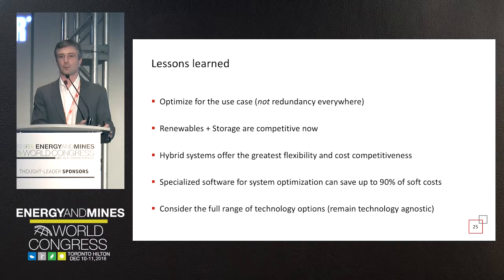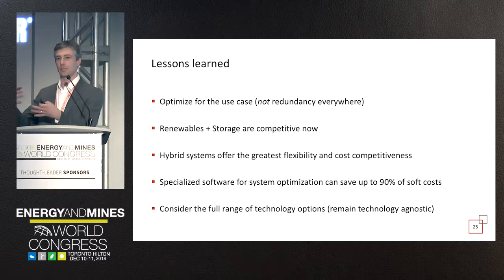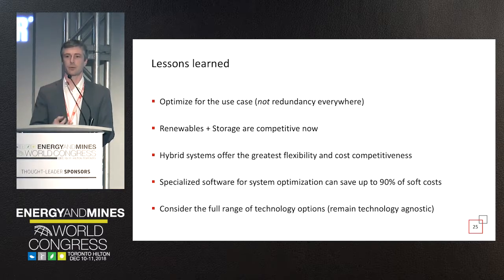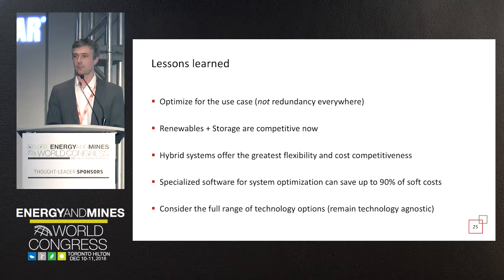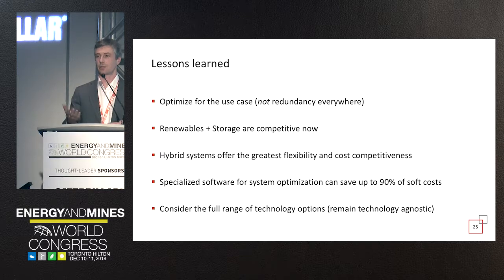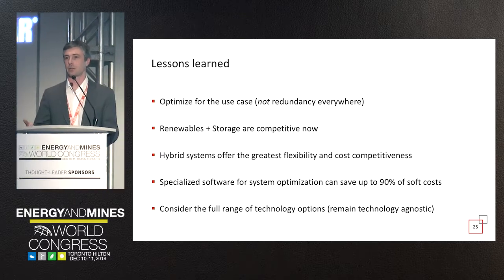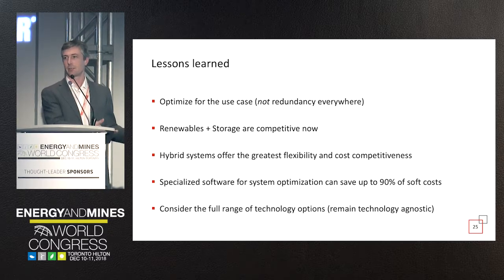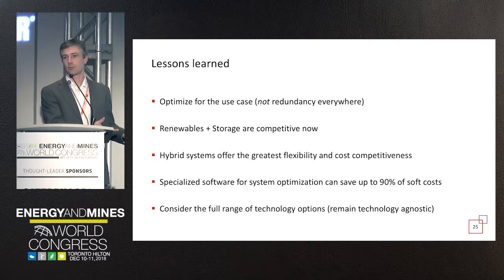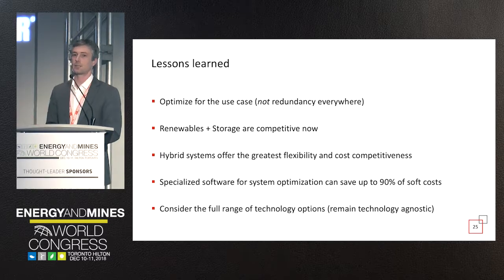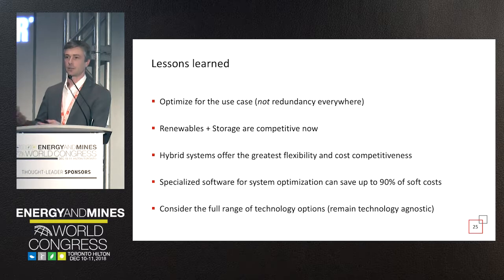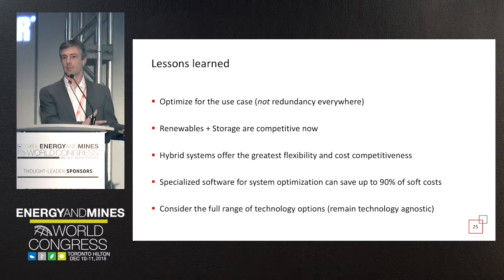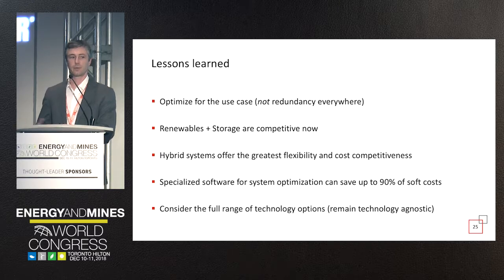Wrapping up on lessons learned through the journey of finding this tool and working with the team that developed it: the best projects are optimized for the use case, as opposed to redundancy everywhere. You may have a different value on reliability depending on your operation — one mine mentioned earlier loses two million dollars a day if they lose service; other cases we've seen show a cost of lost service as low as half a million dollars a day. Depending on your operation, you have to weigh how much you invest in the system versus the cost of a brief outage.